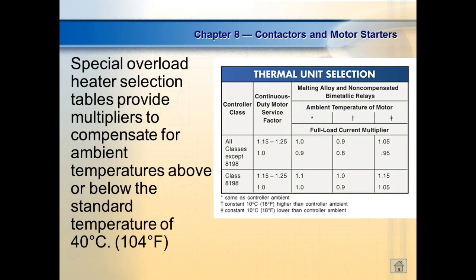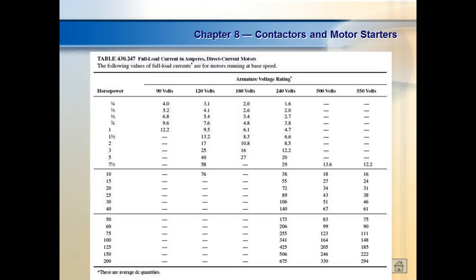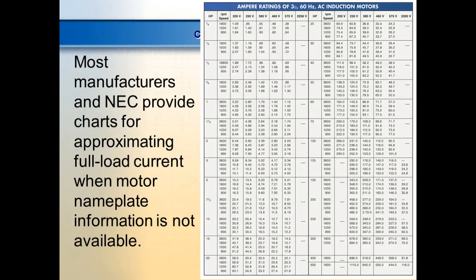What if we don't have a nameplate on our motor? Well, we need to have some way we can get a rule of thumb. We need to know the horsepower of the motor, which we probably do. We need to know the voltage. So there's all types of charts that would give you a rule of thumb that would tell you about what these motors run. This is the chart that's in your book. I don't know how far y'all go to study. This is the chart out of the book I have.